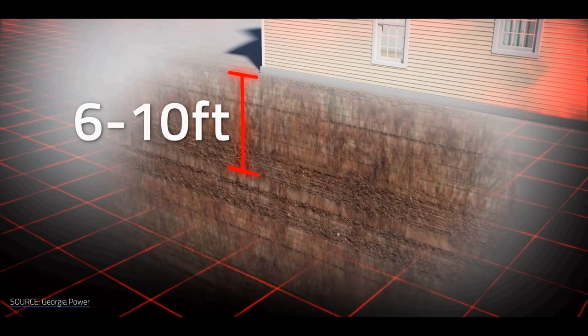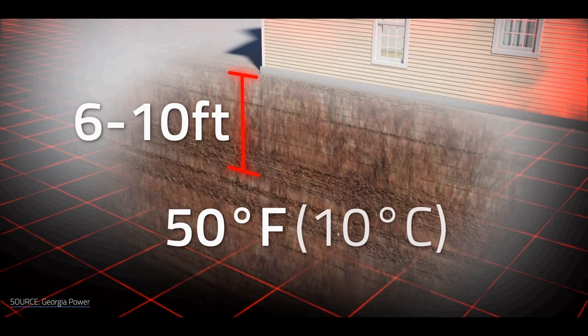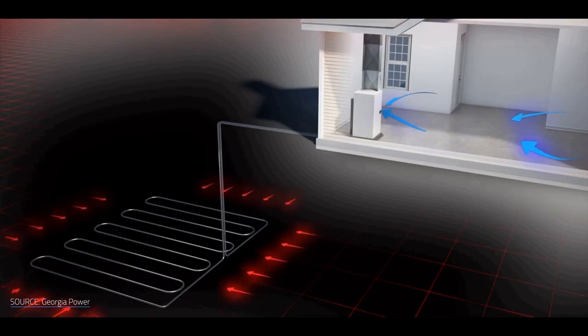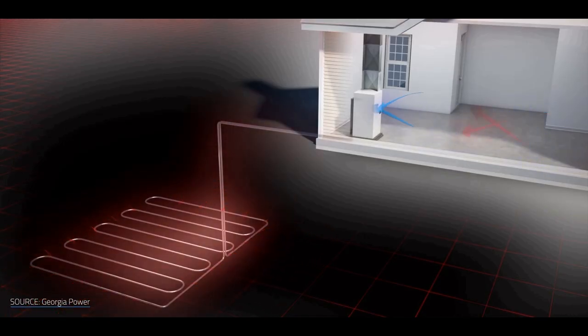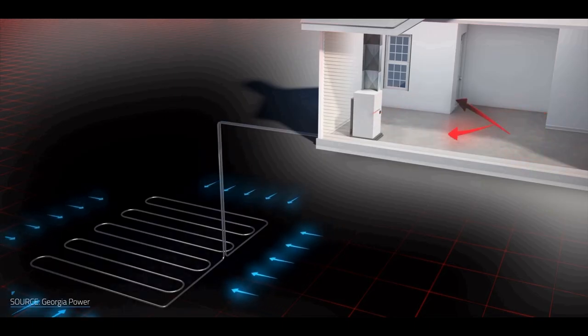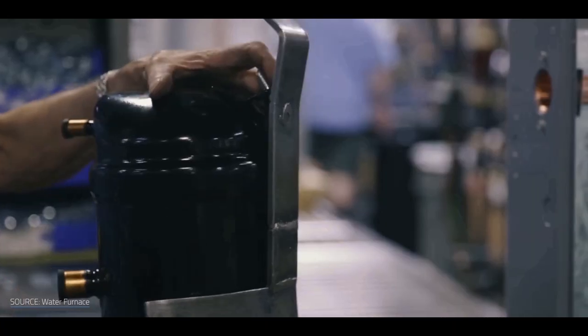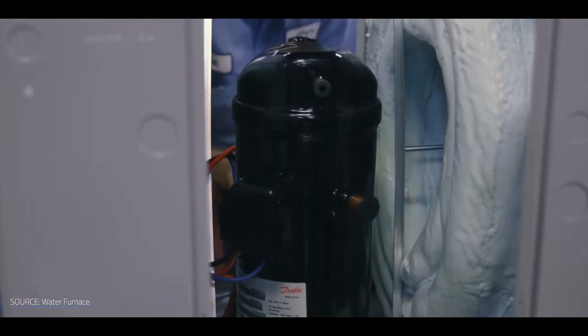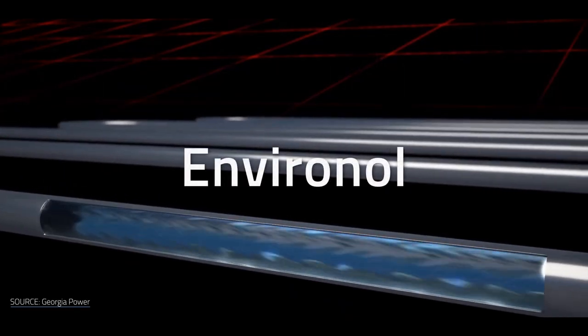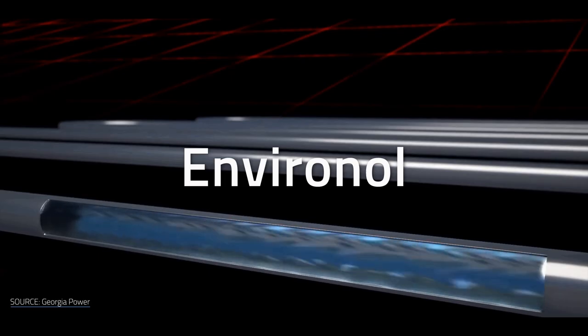Once you get down to about 6 to 10 feet below the surface, the earth becomes a consistent 50 degrees Fahrenheit, or 10 degrees Celsius. That's critical for the efficiency of the heat pump system, because no matter the time of year, we can always count on that 50 degrees to pull heat from in the winter or move heat into during the summer. Exterior air temperature is less of a concern, but by using a compressor, they can boost that heat from 50 degrees up to comfortable temperatures for your home. The liquid pressurized into the tube is Environol, an alcohol-based antifreeze that ensures it won't freeze up in the middle of winter.